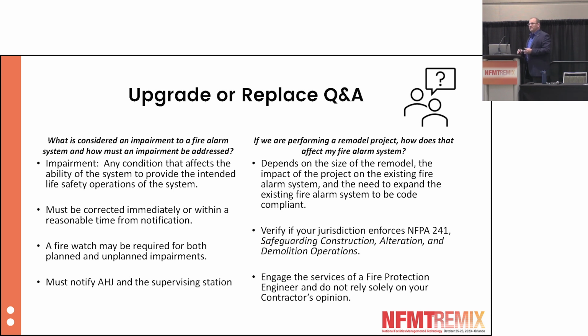This is also true, by the way, if you change monitoring companies. There's a lot of work being done out there right now. You're being monitored by one central station or supervising station, and you decide to switch for price, quality, or any other reason. Well, when that switch happens, the supervising station is required to tell the AHJ that your facility is no longer being monitored by them. That is probably going to prompt the AHJ to visit you as the facility manager to ask, who's monitoring your system? So even from a simple technology switch, a lot of us are losing our analog phone lines and having to switch to cellular or other pathways. That switch is creating a lot of angst in the industry as well.